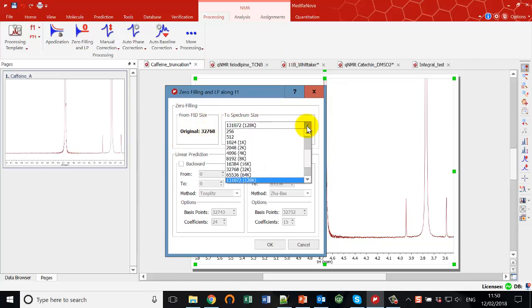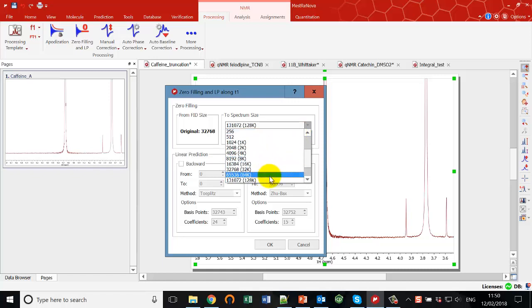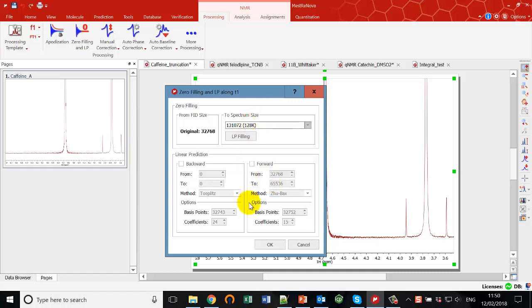Let's first talk about zero filling. This tells me that the original data were collected with 32k points, and two levels of zero filling are what you really ought to be doing. So starting at 32k: one level of zero filling gives 64k, and 128k gives you two levels — and that's what I'm going to do for these data, because I want the peaks to be as well digitized as possible. As a rule of thumb, if you have fewer than 64k data points on a spectrometer less than 600 MHz or so, your peaks will be under-digitized. When collecting data, please collect at least 32 or 64k for proton.